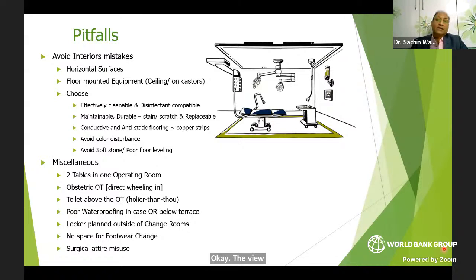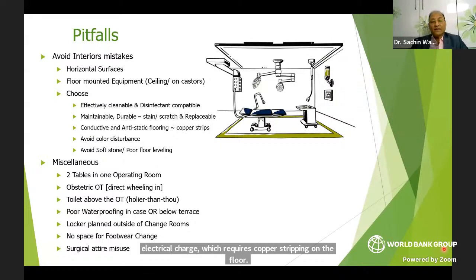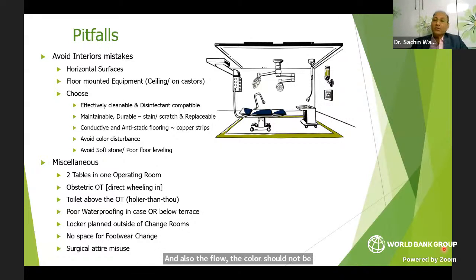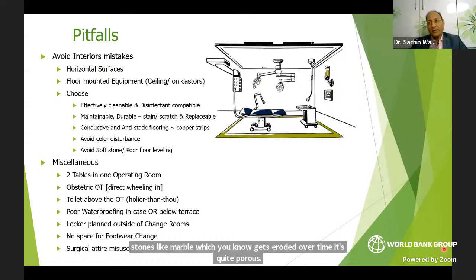We definitely need conductive and anti-static flooring so that the table does not catch electrical charge, which requires copper stripping on the floor. Also, the color should not be disturbing - bare stainless steel OTs emit a lot of glare, and even colors like yellow or green may disturb the surgeon's perception. We have to avoid that, and also avoid soft stones like marble, which get eroded over time since they're quite porous. Floor leveling should be appropriate during construction.